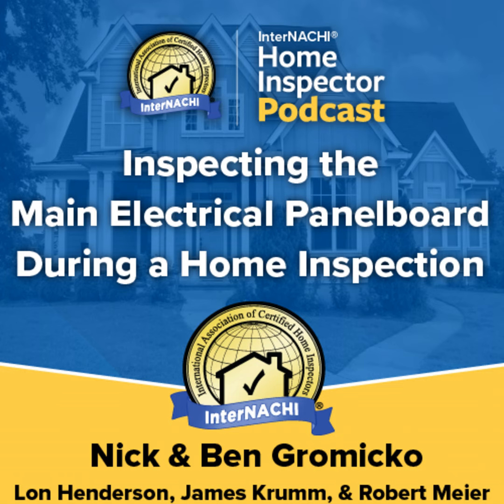Most people refer to all grounded conductors in branch circuits in a dwelling as neutral conductors because they all connect to the grounded neutral conductor in the service, although the code refers to them as grounded conductors. When run underground from the utility pole to the electric meter, service conductors are installed in a buried conduit or run as the underground service entrance cable. Each main service hot wire terminates at a breaker or fuse in the main disconnect, which is the first means of overcurrent protection. The main 240-volt disconnect is housed either in the panel board or in its own separate box installed in combination with or near the meter base.